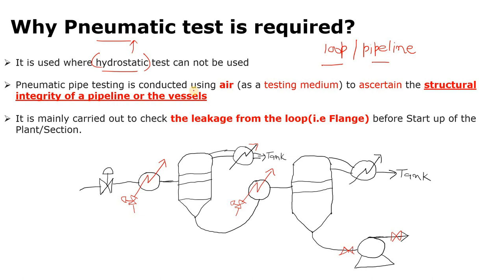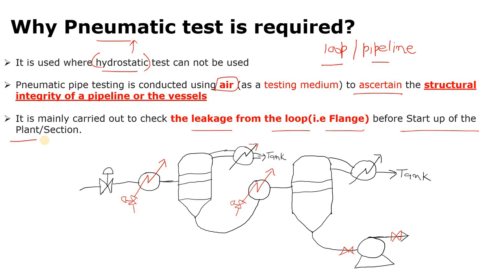Pneumatic pipe testing is conducted using air as the testing medium to ascertain the structural integrity of the pipeline or vessel — meaning whether your vessel or pipeline or loop is okay or not, i.e., whether there is any leakage or not. It is mainly carried out to check leakage from the loop, and mainly at the flanges, before startup of the plant or section.